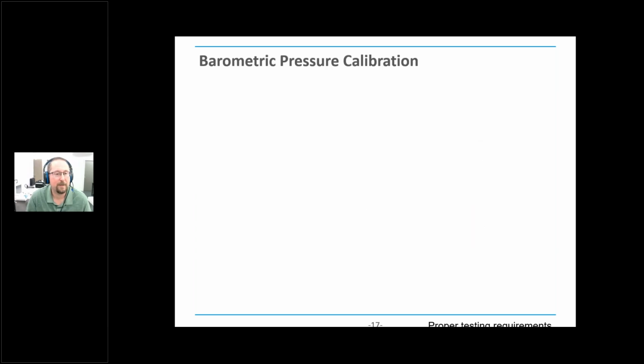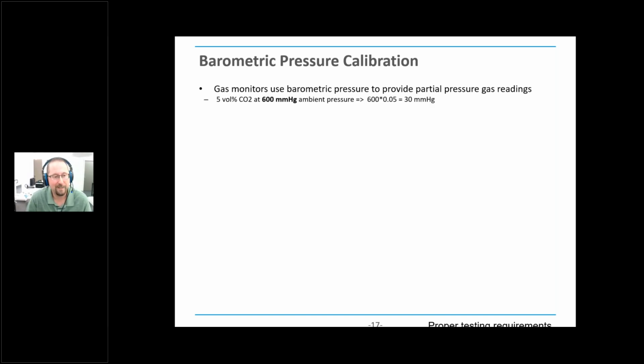All right, so barometric pressure is another one. We see some issues here. Barometric pressure, every device has a sensor in it to measure barometric pressure. That's what allows them to convert from volume percent to the partial pressure. So for example, 5% CO2, which is what the sensor is actually reading, at 600 millimeters of mercury, that's going to give you a reading of 30 millimeters of mercury. So that's the reading that the doctor's actually going to see.